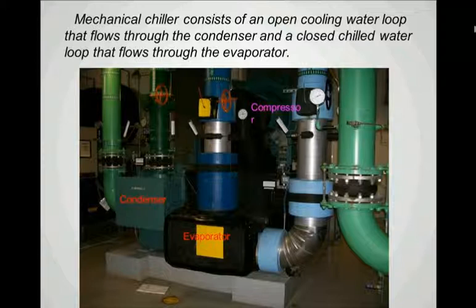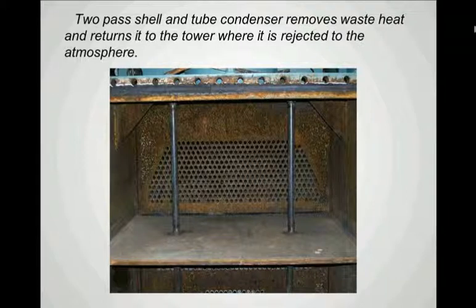This happens to be a two-pass shell and tube condenser section of the mechanical chiller. And water enters this at the bottom of the chiller condenser, passes through the ID of the condenser tubes, makes a bend and comes back through the condenser, and then exits, where that water that has picked up the heat from the condenser is sent back to the cooling tower. And this process gets repeated over and over as the condenser water cycles back through the condenser, up to the cooling tower, back to the condenser again. Again, in doing so, it conserves water and improves overall the efficiency of water usage.